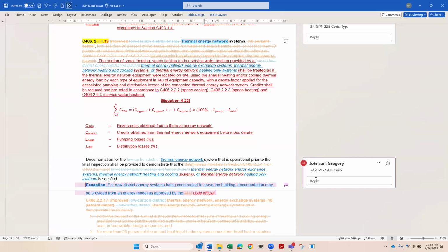Also, there's an efficiency loss in pumping and distribution loads on a thermal energy network. So we have to derate it — while you aggregate out and get high efficiencies for your equipment because of heat recovery, you have to derate those credits by the losses from pumping and distribution.